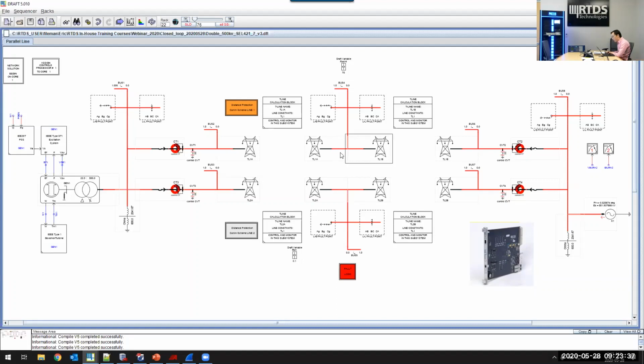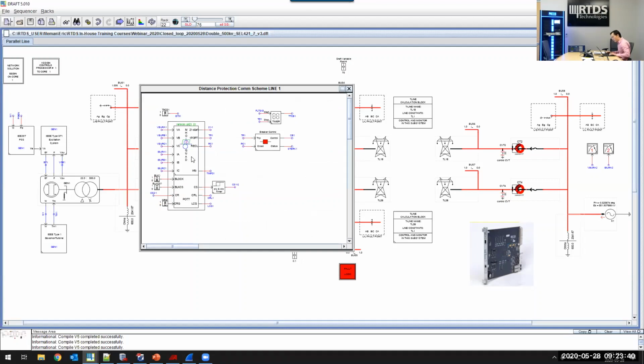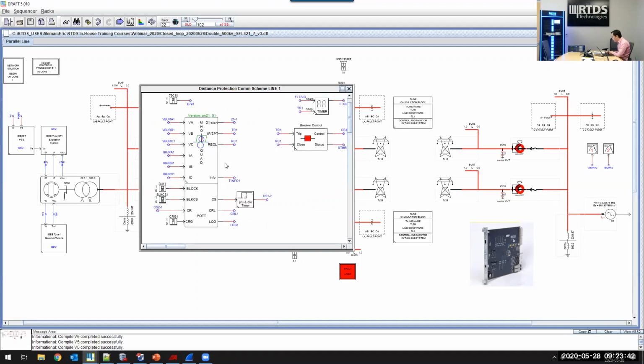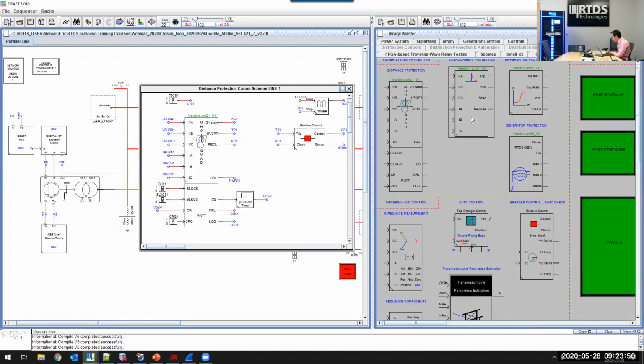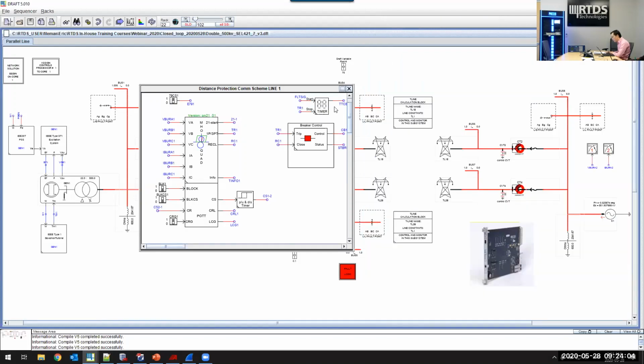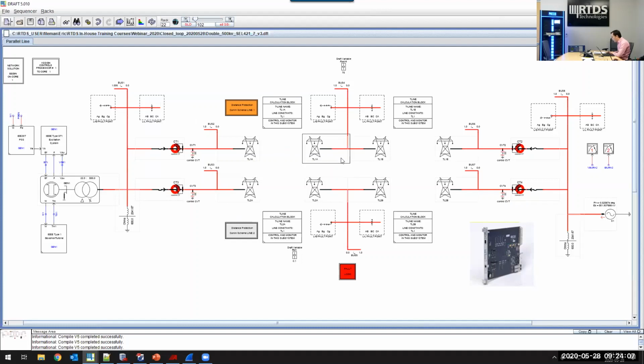The other 3 breakers are protected by using the distance protection relay component that can be found in the protection and automation library. The relay components in the protection and automation library were developed based on generic protection functions. They may be used when physical relays are not accessible. So the top line is the focus for the demo, and we would like to apply faults along the line so that we may observe and validate the response from the physical relays.